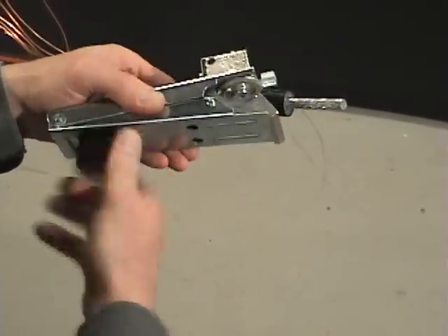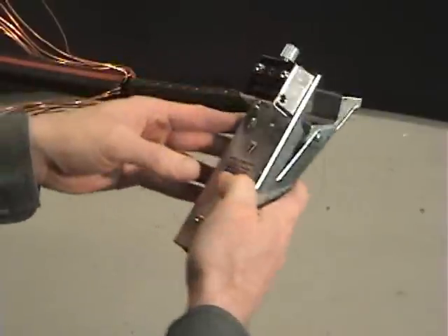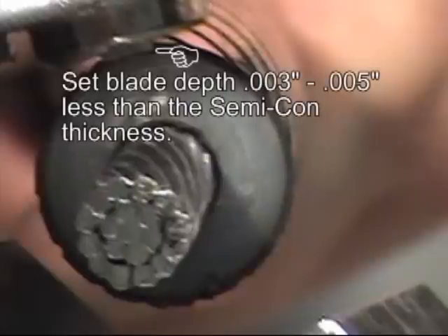Verify that the blade lever is in the square cut position and check the blade depth on a scrap piece of cable if one is available, or by visually checking the blade at the end of the cable. The blade depth should be set to approximately 3 to 5 thousandths less than the Semi-Con thickness.